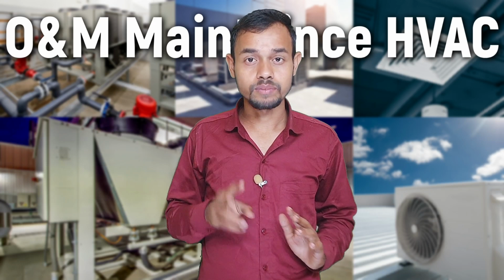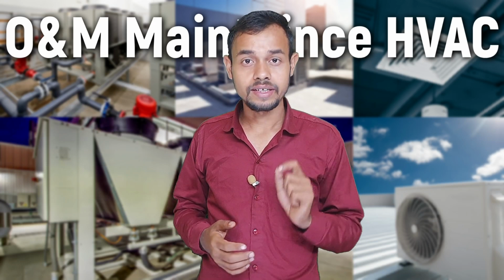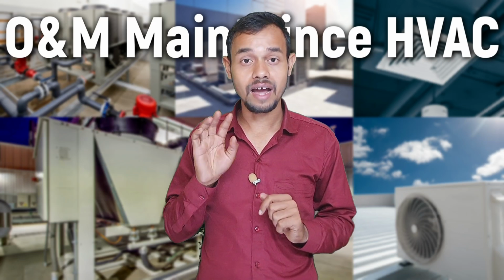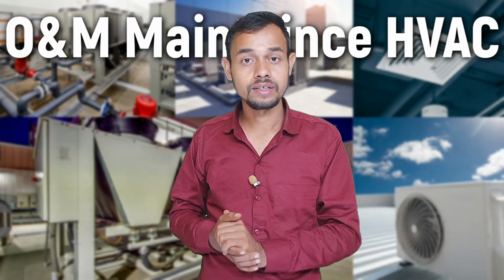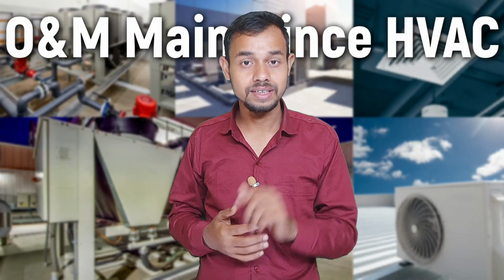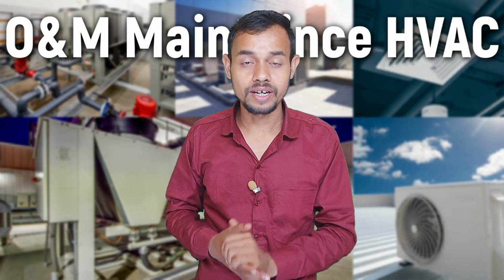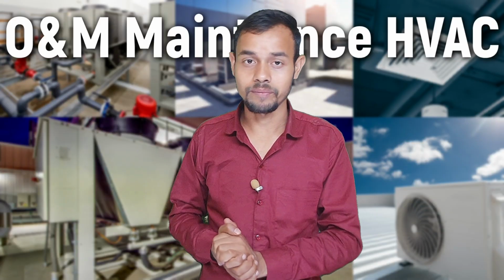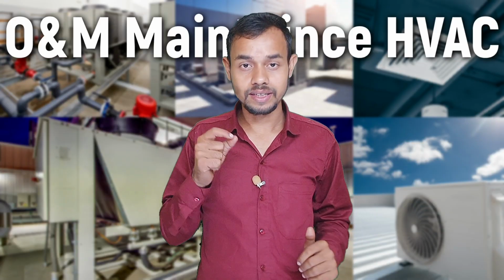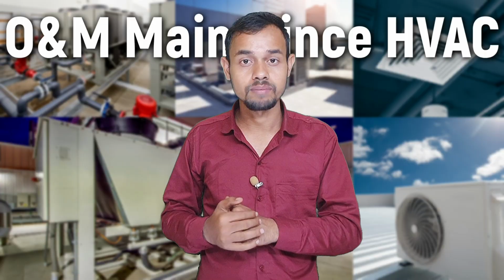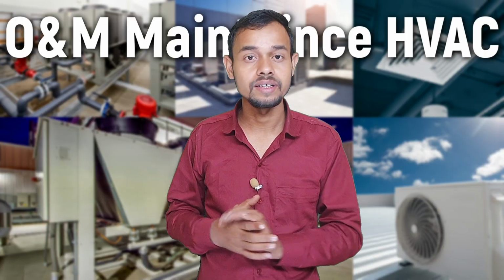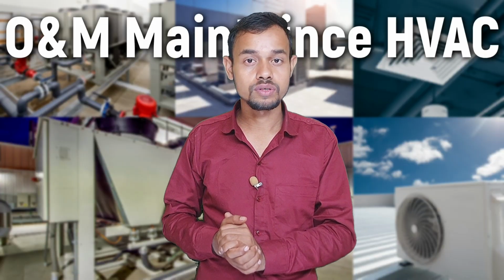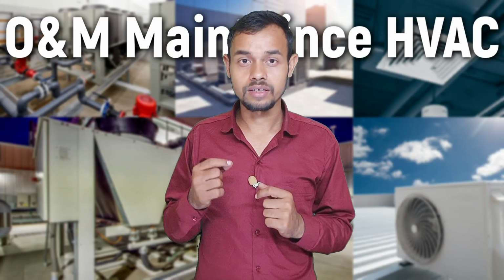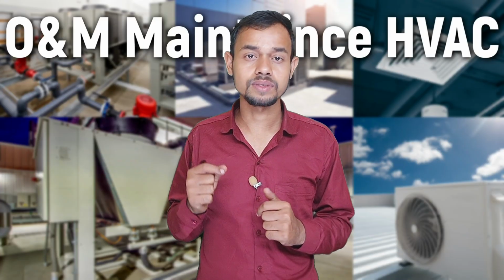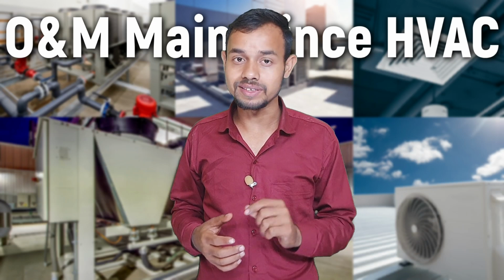Second is checking pumps, cooling towers, and AHUs: any unusual sounds, higher or lower current, vibration, suction and discharge pressure, and water flow. Once in a while a pump starts vibrating slightly, the operator catches it early, otherwise in a couple of hours the pump seal would have fully leaked. This is proactive operation.